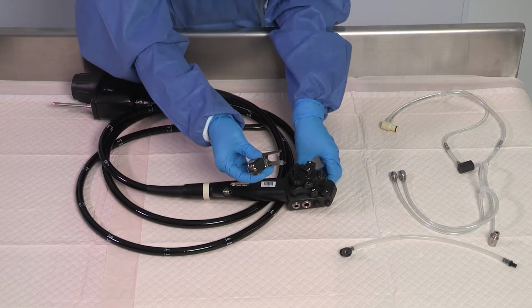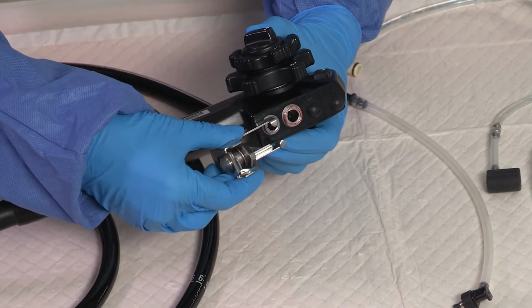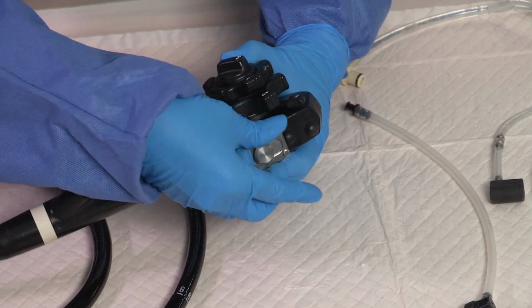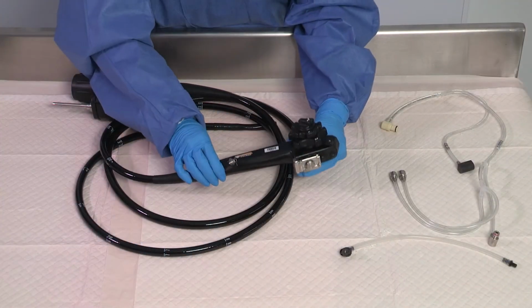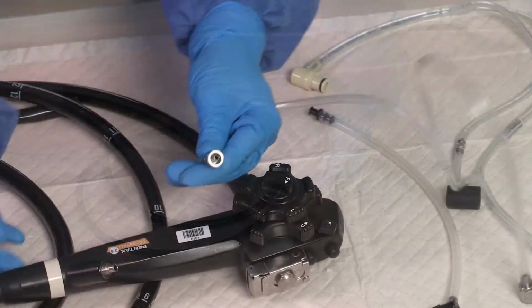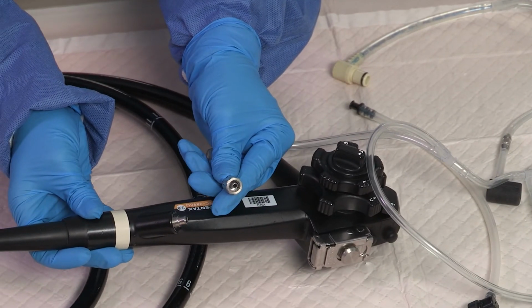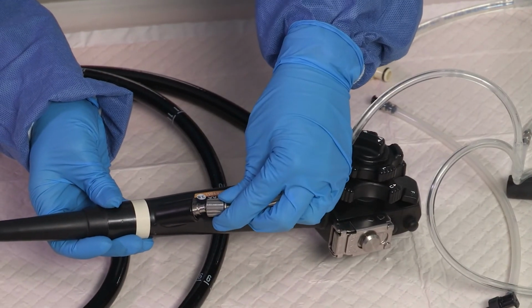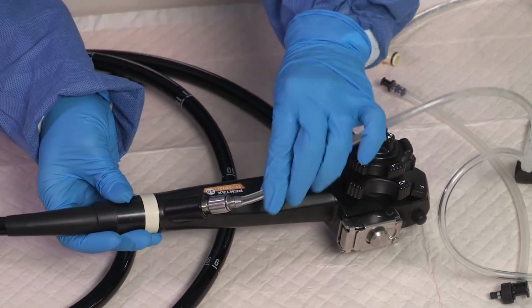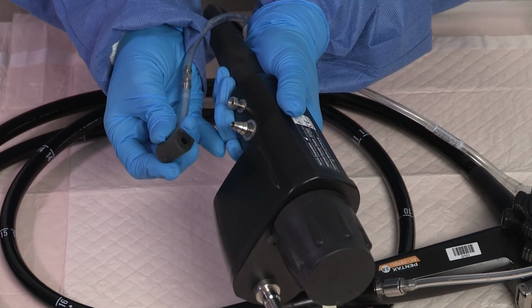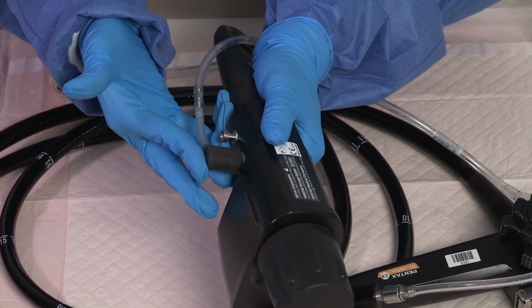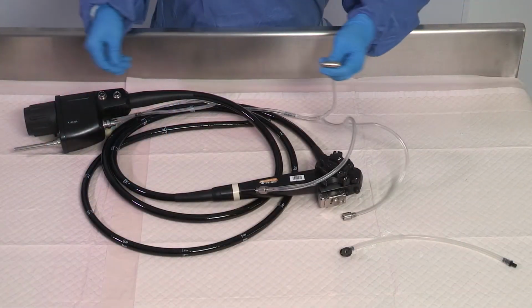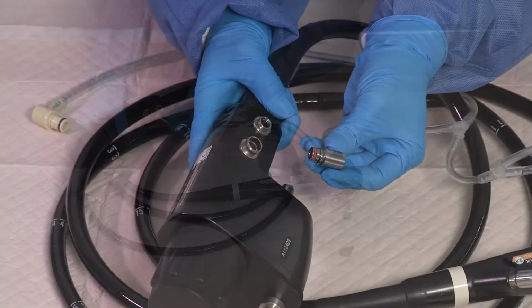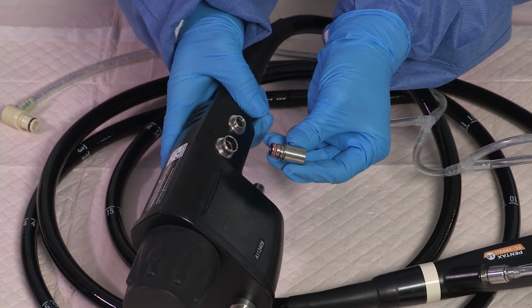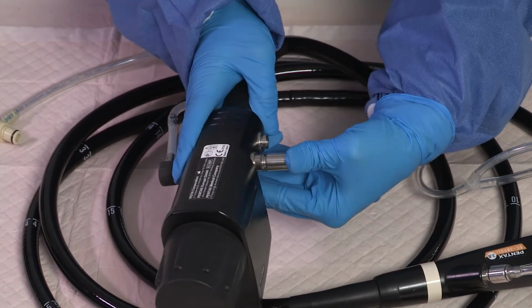Starting with the air, water, and suction cylinders, attach the Pentax cleaning adapter following the manufacturer's IFU in order to block fluid flow out of the air, water, and suction cylinders. Attach the biopsy inlet connector by aligning the hookup's luer fitting on the instrument channel's opening. Push and turn clockwise to fully engage. To attach the hookup suction connector, align the connector with the suction barb on the endoscope. Push onto the barb until fully engaged. The air-water connector is attached by aligning it with the endoscope's air-water port and pushing toward the endoscope until fully engaged.